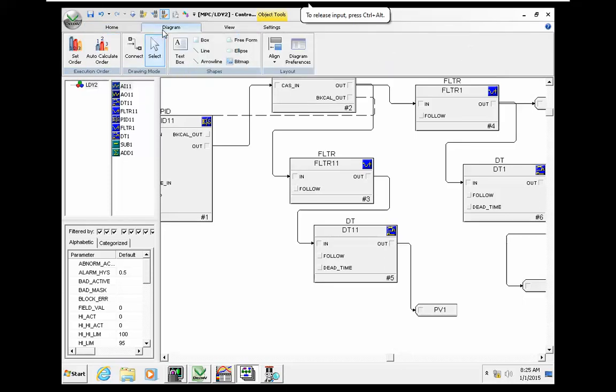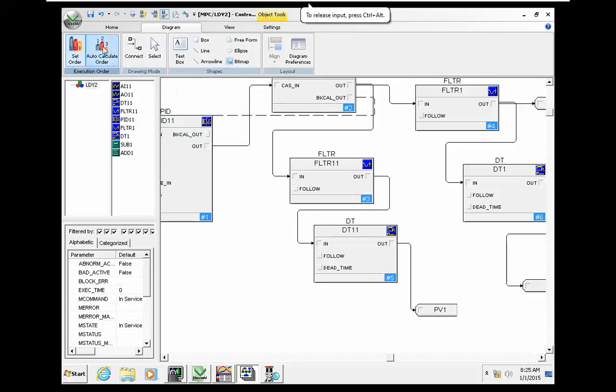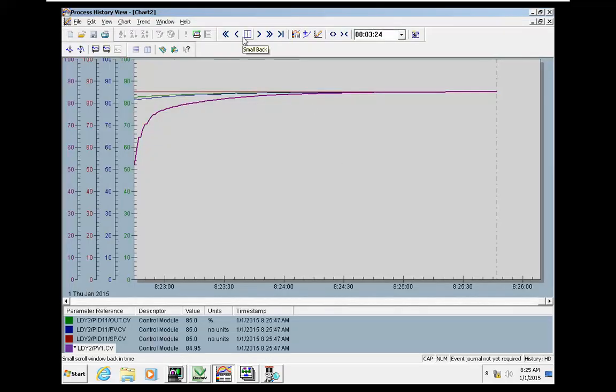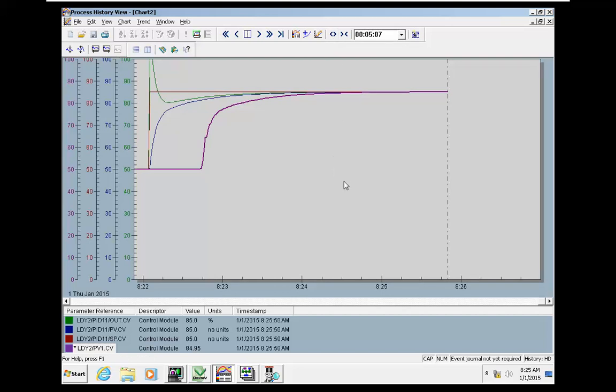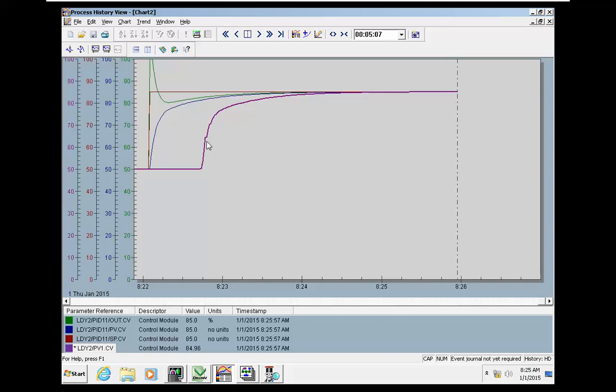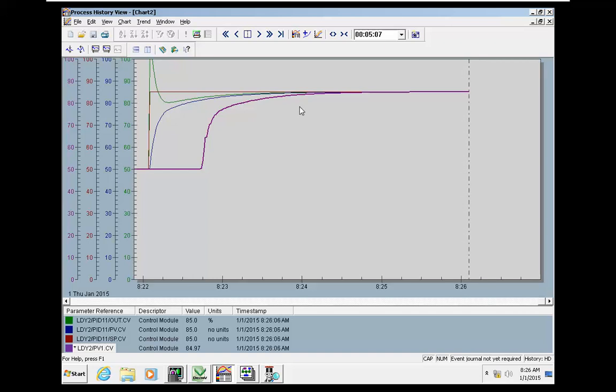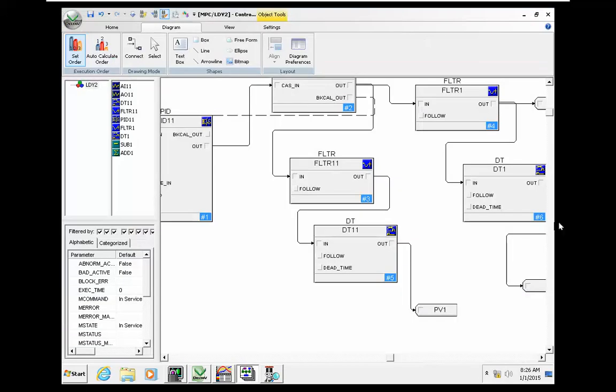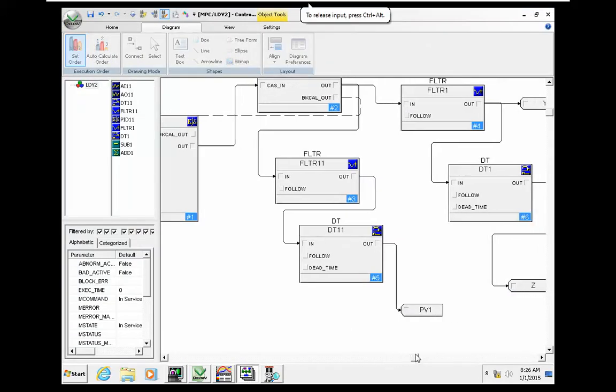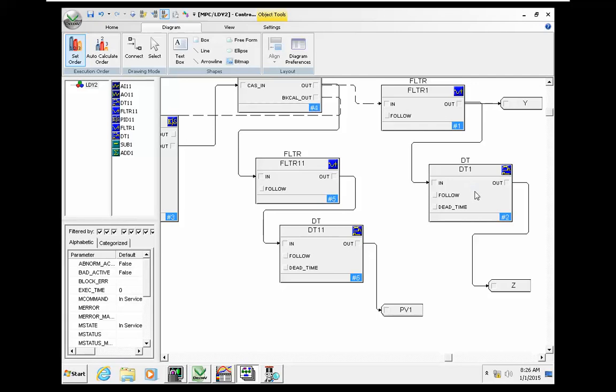This is the actual field model and this is the compensated model. I created some math functions — subtract and addition — to produce the compensated analog input, which is fed to the PID controller. To check and set the block order, simply select 'Set Order' from the diagram and select the proper sequence. The response is very satisfactory — you can see the compensated value versus the actual process value.